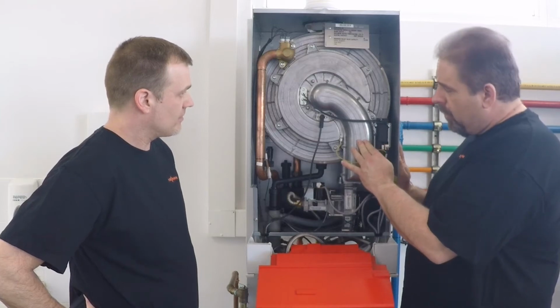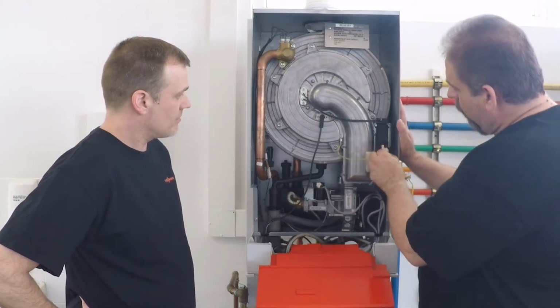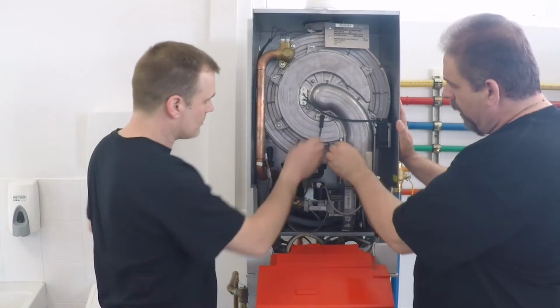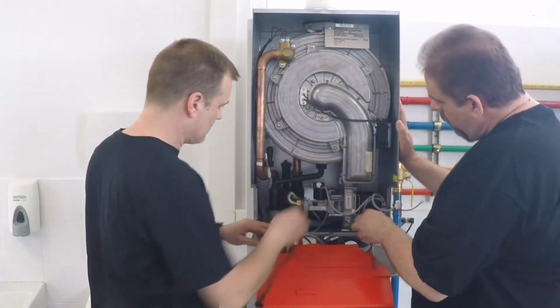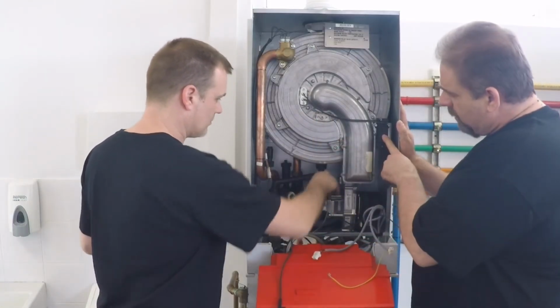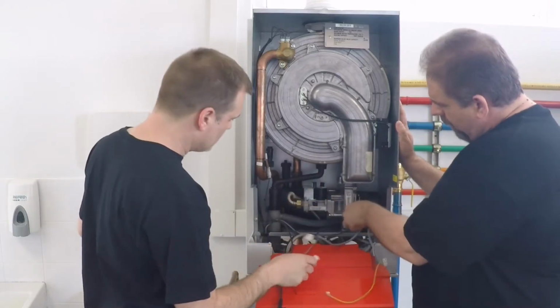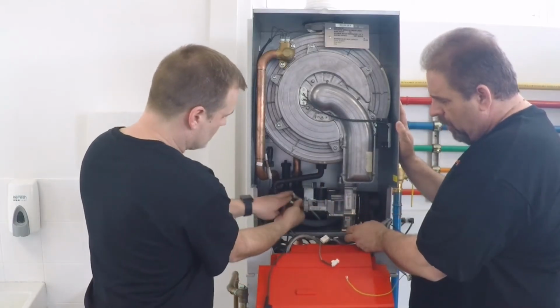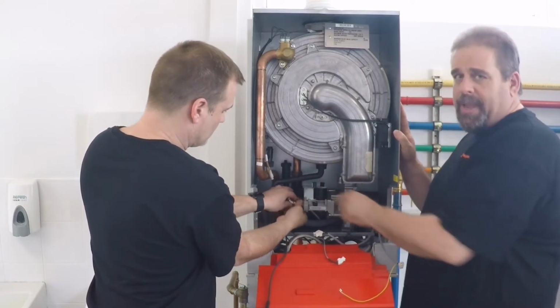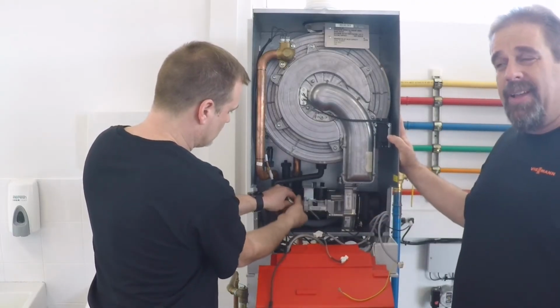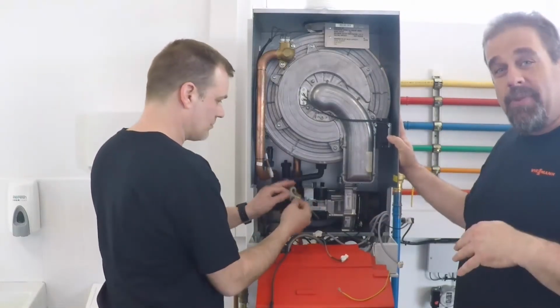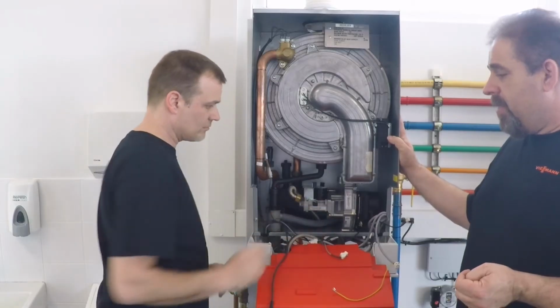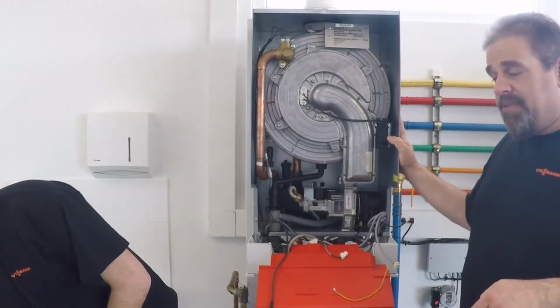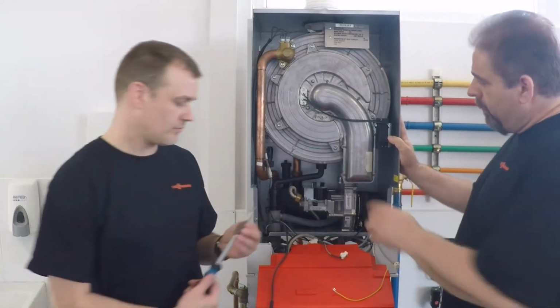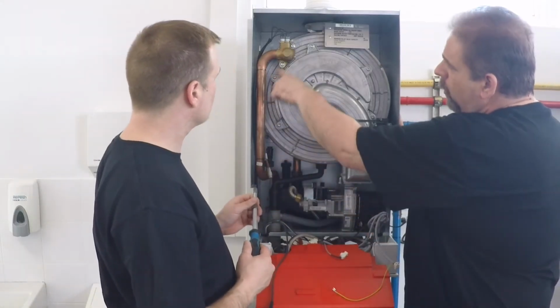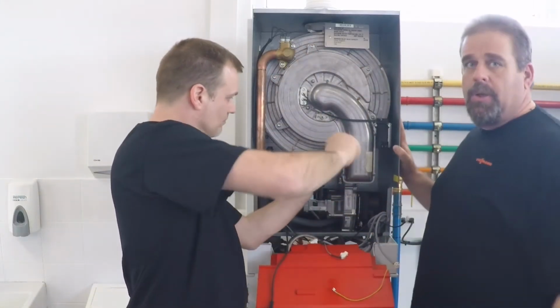assembly. So we have Molex plugs that only plug into one place. We can go ahead and unplug those. We can unplug them from our transformer, from our gas valve, and from our variable speed fan. And then we'll remove the corrugated gas line from the gas valve, of course after shutting the gas off, which we've already done. Then with our Vitodens kit, we'll replace that Phillips bit with a torx bit, and we're going to remove 6 torx screws from the heat exchanger.